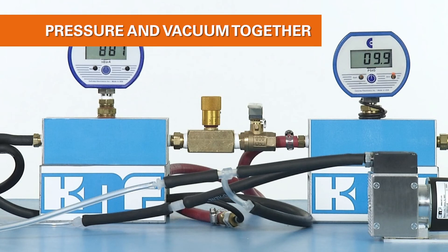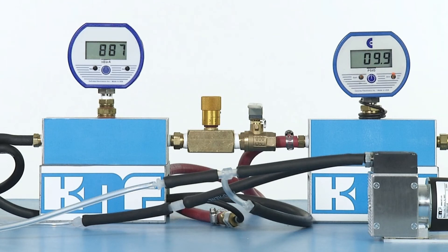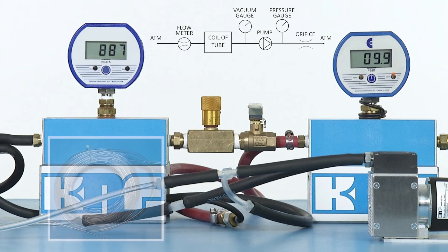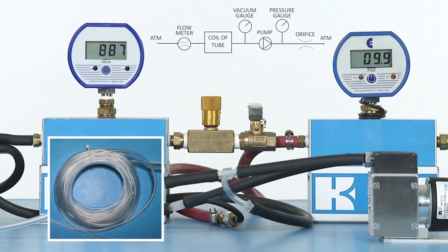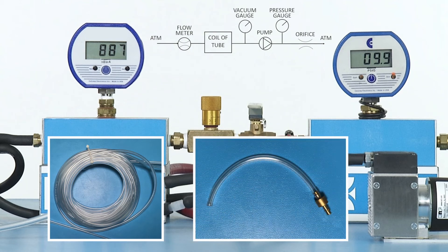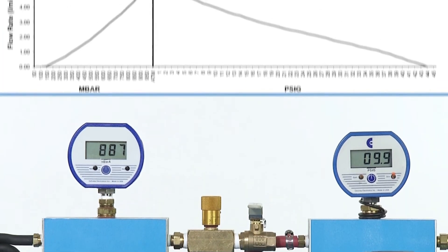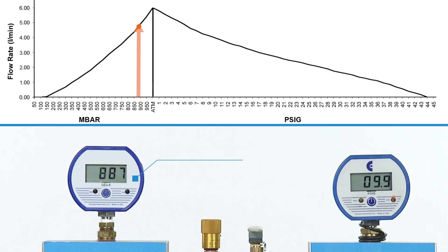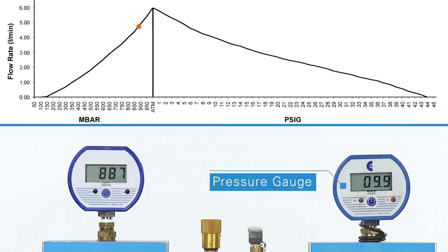What happens to the flow rate when there is restriction on both sides of the pump? This example demonstrates how to use the flow curve to estimate the flow rate performance of a pump when both vacuum and pressure conditions exist. A long length of tubing with a small inside diameter is connected to the inlet side of the pump, and a small restrictive orifice is connected to the outlet side. By teeing in the vacuum gauge, the display shows 887 millibar absolute of restriction created by the tubing on the inlet. On the outlet side, approximately 10 PSIG is measured on the pressure gauge teed in between the pump and the orifice.